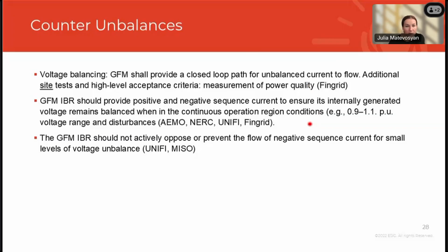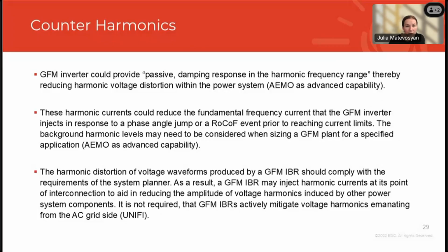And then grid forming should not actively oppose the flow of negative sequence current for small levels of voltage imbalance. So that's what UNIFI and MISO define. For harmonics, basically the inverter can provide a passive damping response for the harmonic frequency range, thereby reducing harmonic voltage distortion. That's what AEMO advanced capability requires.